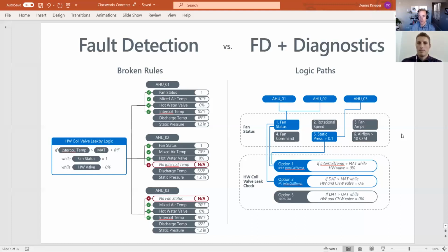So the air handler that doesn't have a fan status—what you're basically saying is that since it does have a static pressure sensor, we're able to use that as a proxy to say the air handler's on, and that becomes the rule.